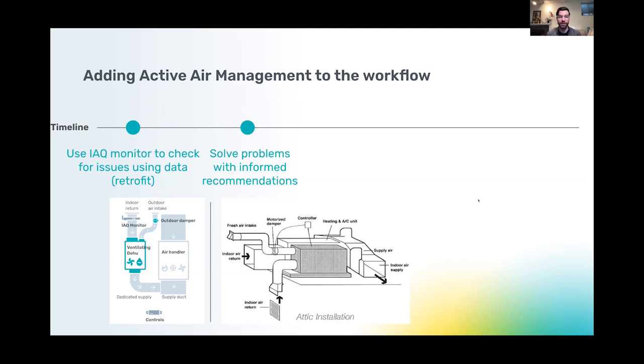But one of the reasons this is so effective is it's going to keep the air handler and the air conditioner running longer because it's producing some of the heat with the heat pump. So it's very energy efficient. And so the air conditioner is going to be on longer. Your comfort is going to get better because the air conditioner is running longer and because you're better controlling humidity, and humidity has a big impact on comfort. So this is a solution that improves comfort. It's a solution that controls dehumidification.